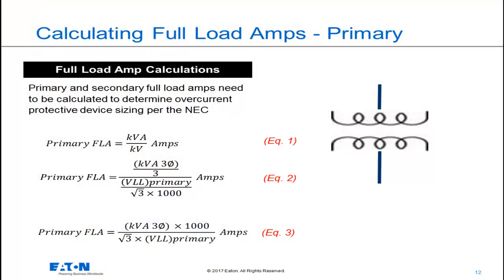The full load amps of a transformer is usually printed on the nameplate of the transformer, but in the design phase, we won't have that actual device in front of us, so we have to learn how to calculate this information by hand.